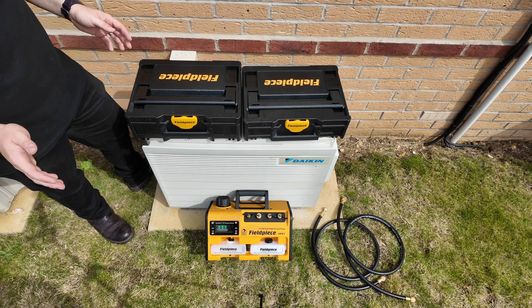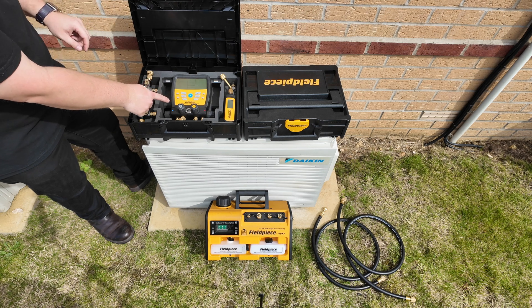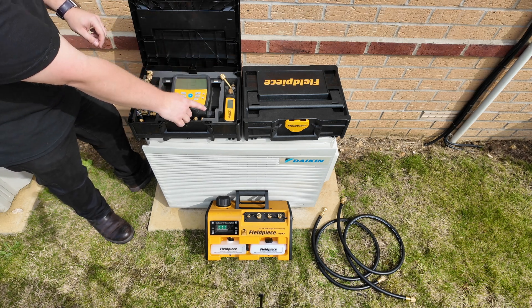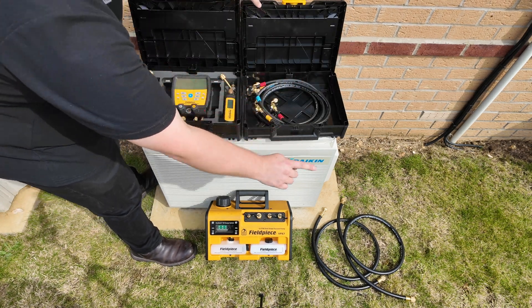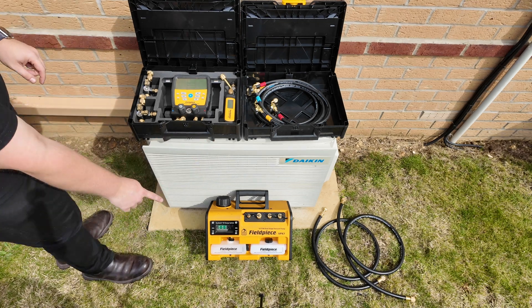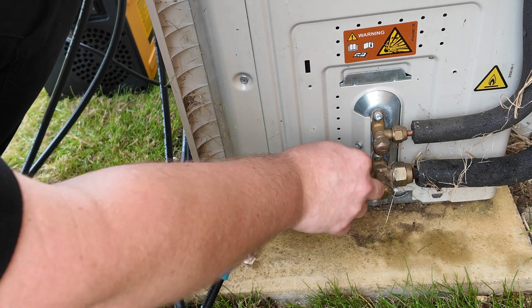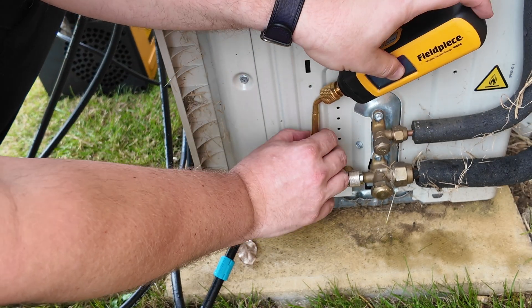To carry out the evacuation we're going to need some tools. We're going to need the Fieldpiece digital manifold, the Fieldpiece valve core removal tool, the Fieldpiece wireless vacuum gauge, some charging hoses as well as some vacuum hoses, and finally a Fieldpiece vacuum pump. Firstly I'm going to add the Fieldpiece vacuum gauge to the system by utilizing the additional port on the valve core removal tool.